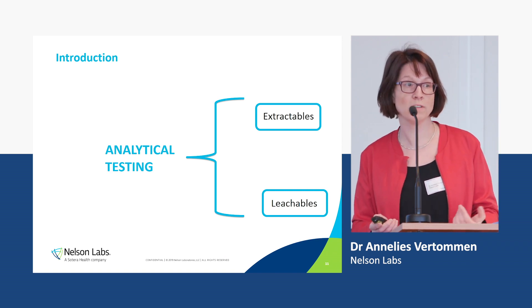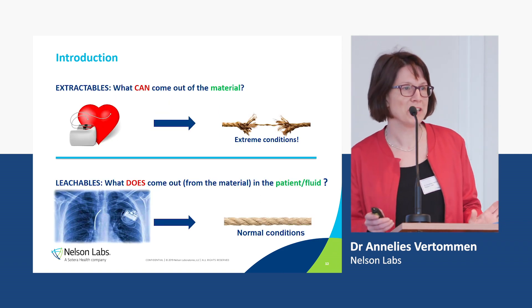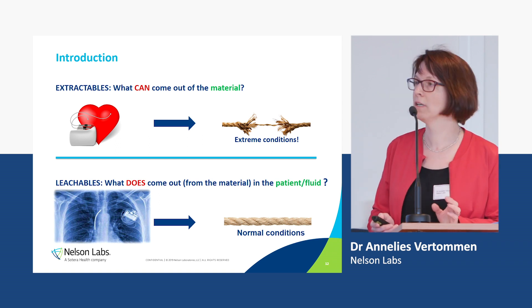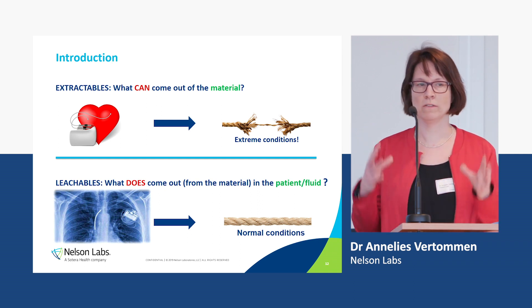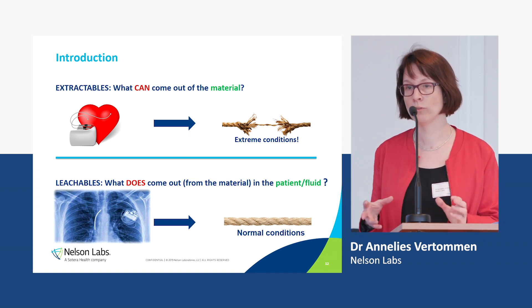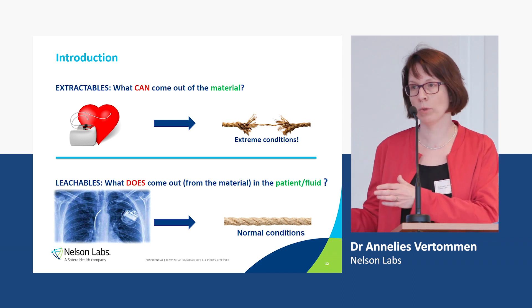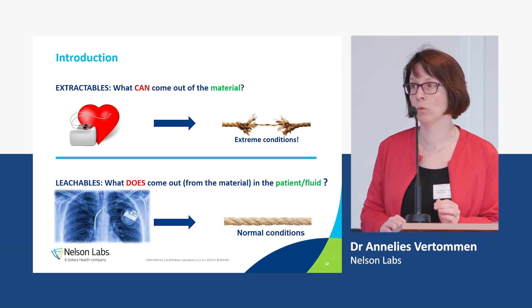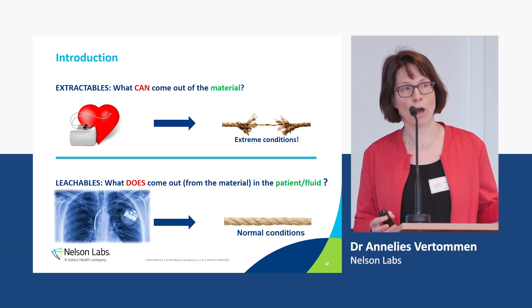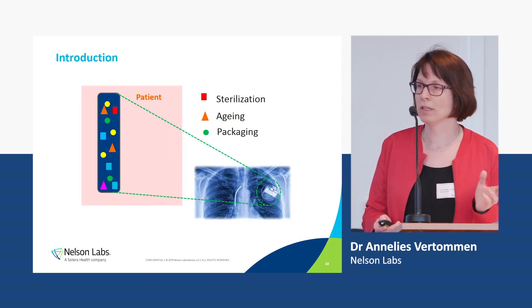Therefore, these tests require analytical testing. Let's go to the definitions of extractables and leachables, because there is still some confusion about these concepts. It's quite simple: extractables are the set of compounds which can be extracted from your medical device under worst-case conditions — the whole set of compounds which have the potential to end up in a patient, but it does not mean that they will end up in a patient. Leachables are actually the compounds that come off your material and will end up in your patient under normal use conditions.